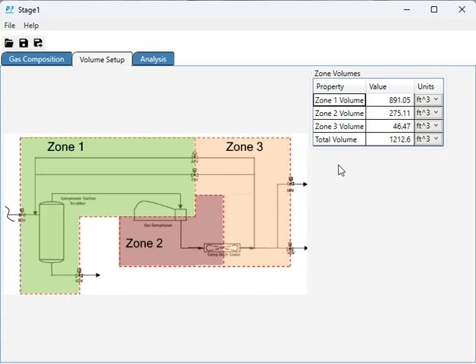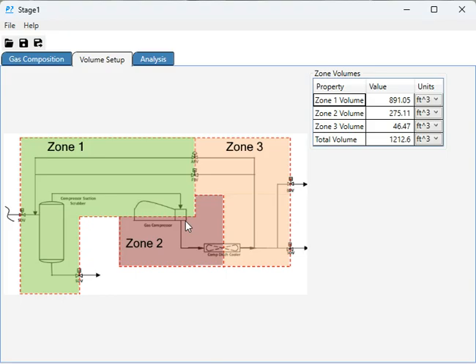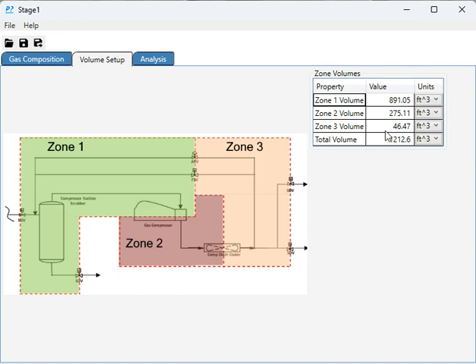You would solve these volumes using your isometric drawings or, worst-case scenario, having to walk down the piping system and take measurements. The compressor itself, its volume is quite small, and I typically estimate that as a third of the volume of the external dimensions of the compressor casing. You could probably just ignore it, but that's what I do. So you'd have volumes in the three sections and a total volume.